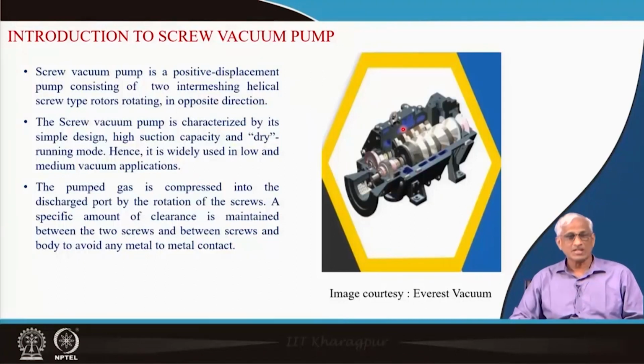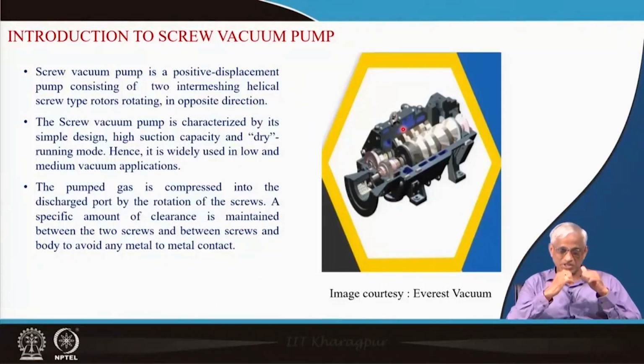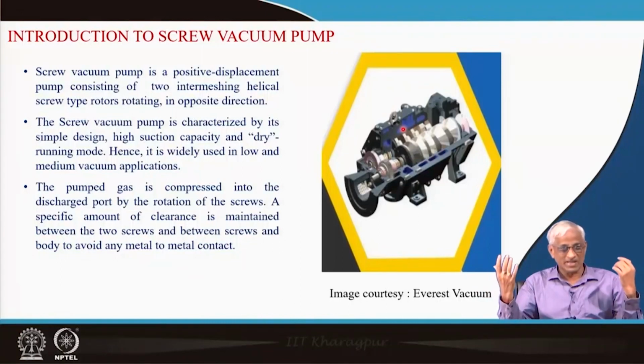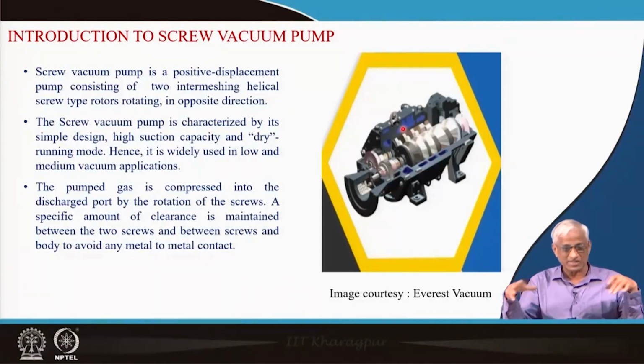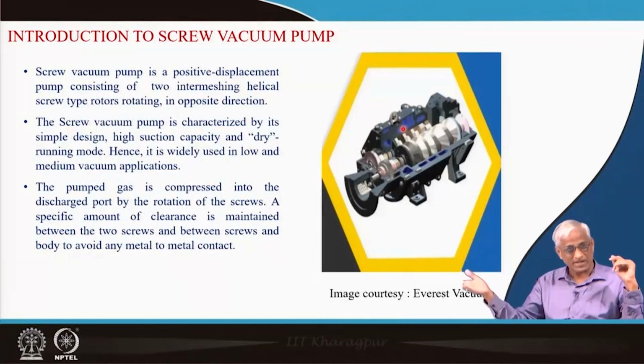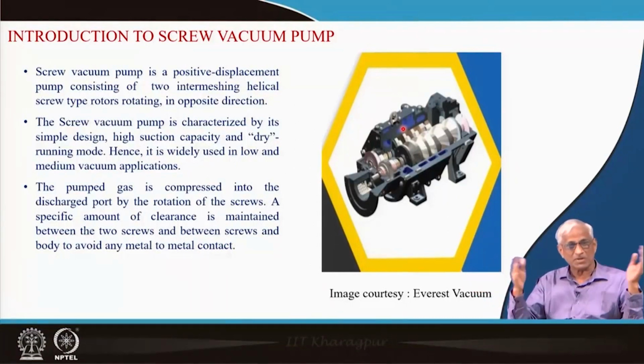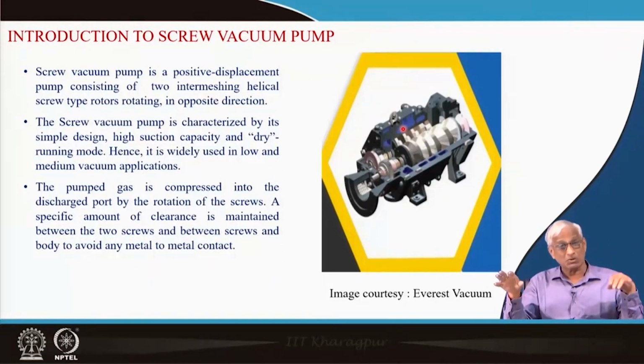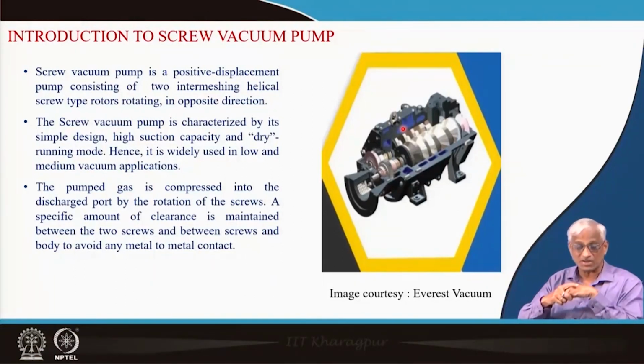Basically, the screw pump contains two intermeshing, synchronously rotating screws, properly supported by bearings, connected through one shaft to the motor but with a synchronizing gear assembly, properly lubricated. Different chambers are isolated using seals, and temperatures of those seals have to be maintained if necessary by purging, etc.